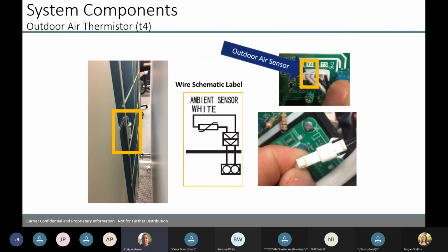Outdoor air thermistor. All that is doing is reading your outdoor air temperature. It helps if the unit is in a heating mode and it's 87 degrees outside. We do not want that unit to go into a heating mode. It is going to stop that unit from going into a heating mode. That's all that temperature sensor is doing. It's telling us if it's minus 17 outside or it's 87 degrees outside.